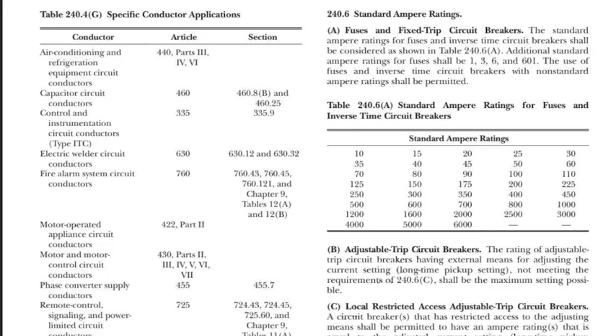So let me address that question for a second. We like to not load a breaker more than 80%, but that's for our branch circuits - our branch circuit loads, we try to do that too, for breakers like our 20 amp, 30 amp, 50 amp breakers and so on. A main breaker, you can just load it straight up to whatever its rating is. Why can we do that? Because we've already done a bunch of calculating and reducing wattages when needed, etc., to be able to just pick this breaker. We don't have to do anything else to the load on a dwelling unit.